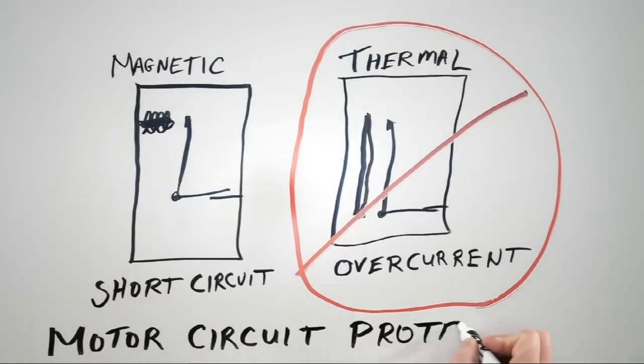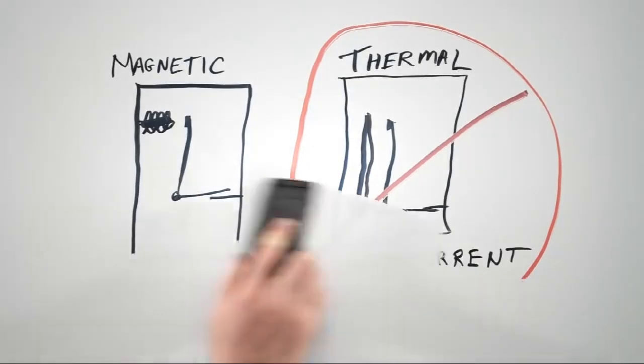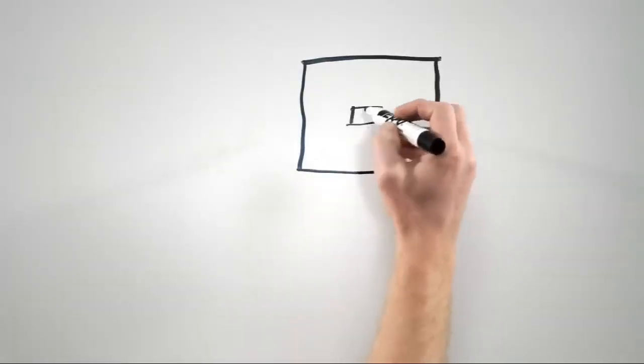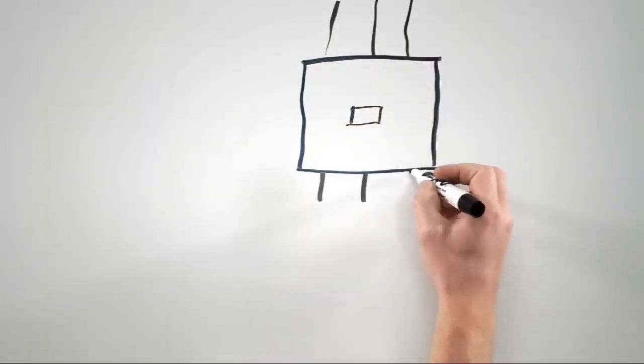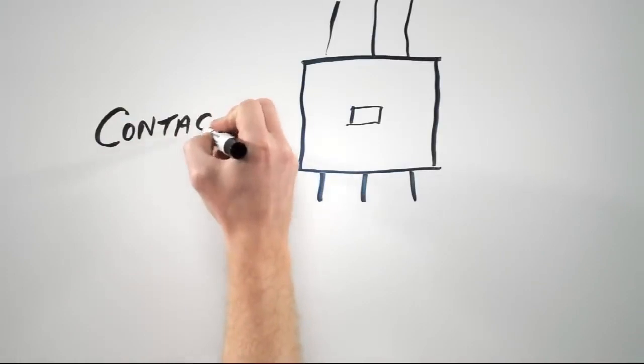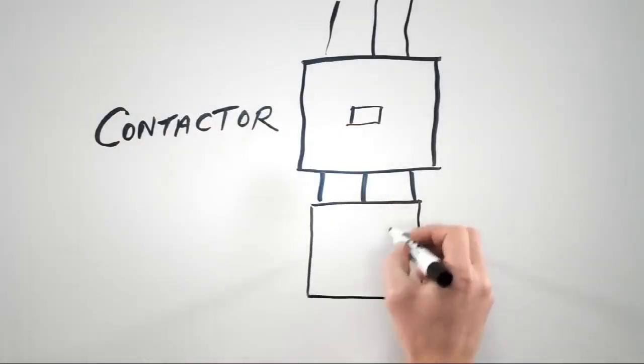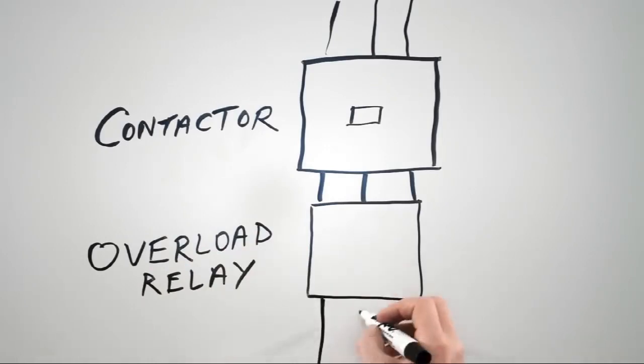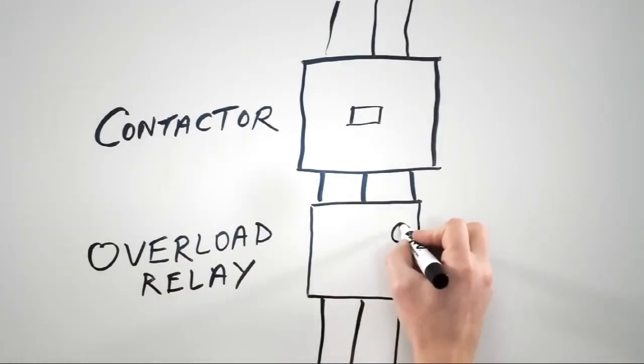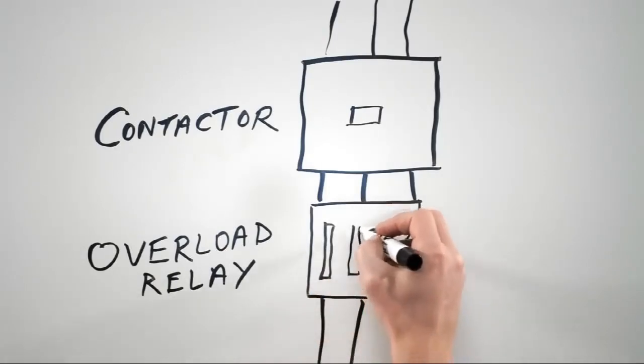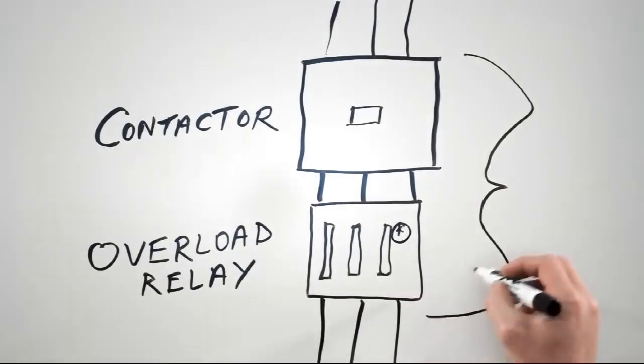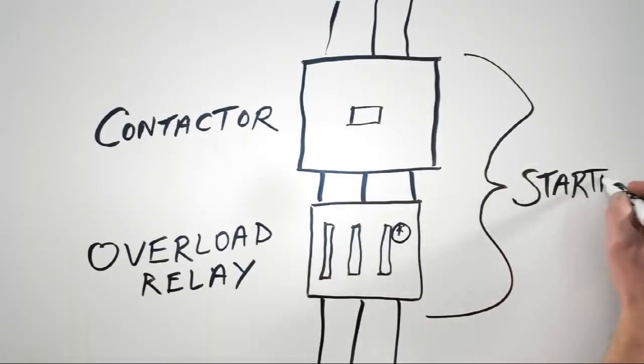Frequently you'll see Eaton's version called an HMCP, with the H standing for High Interrupting. So, if we get rid of the over current protection provided by the molded case breaker, we still need to find a way to protect the motor from an overload condition. Here we've got a contactor with our power coming in the top and out the bottom. But now let's add a new component to the contactor. This is called an Overload Relay. The Overload Relay has three bimetal strips inside that are designed to heat up at the same rate as the windings of the motor. This is different from the bimetals inside the breaker, because those bimetals didn't know to ignore the inrush when you start the motor. When you pair an Overload Relay with a contactor, we call this a starter.